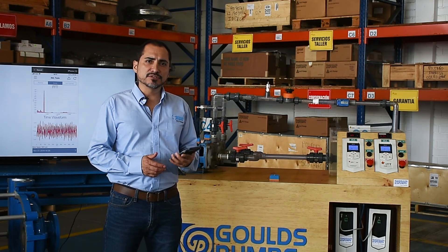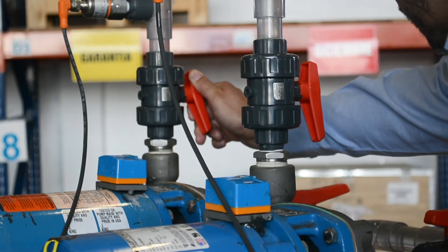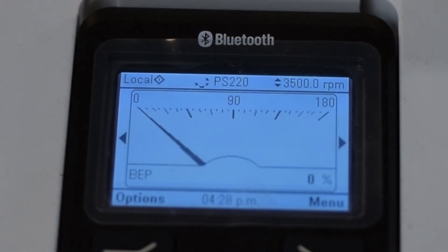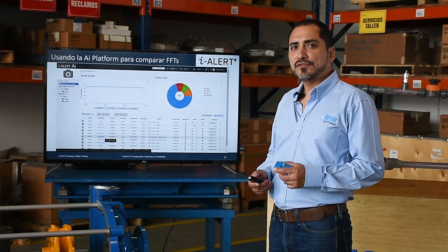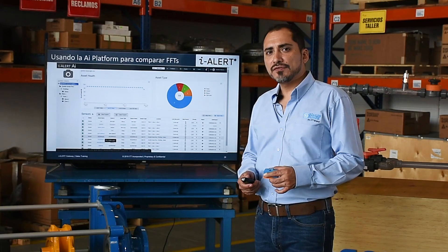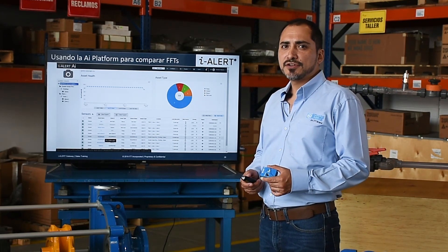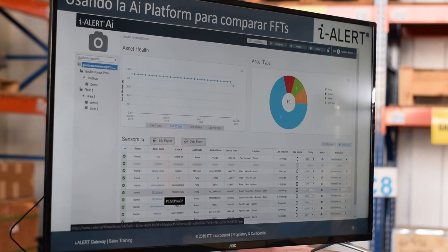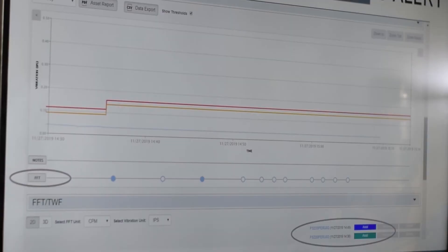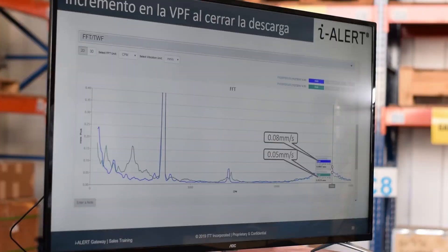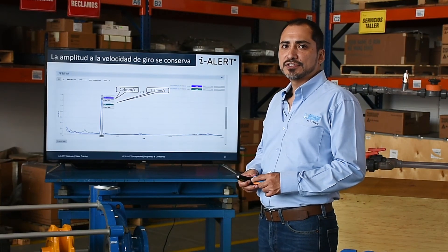Let's now look at the spectrum of the operation with the blocked discharge. We close the discharge valve and take a new spectrum. Now the pump is running at 0% of BEP. We observe in the FFT that the amplitude at the vane pass frequency has increased from 0.05 to 0.08 mm per second. This can better be analyzed through the AI platform, which shows the information of all the sensors in a plant in a single asset management system. By selecting two FFTs — one close to the BEP and the other at shutoff — we notice the amplitude has increased from 0.05 to 0.08 mm per second, whereas the amplitude at the speed of rotation is preserved.